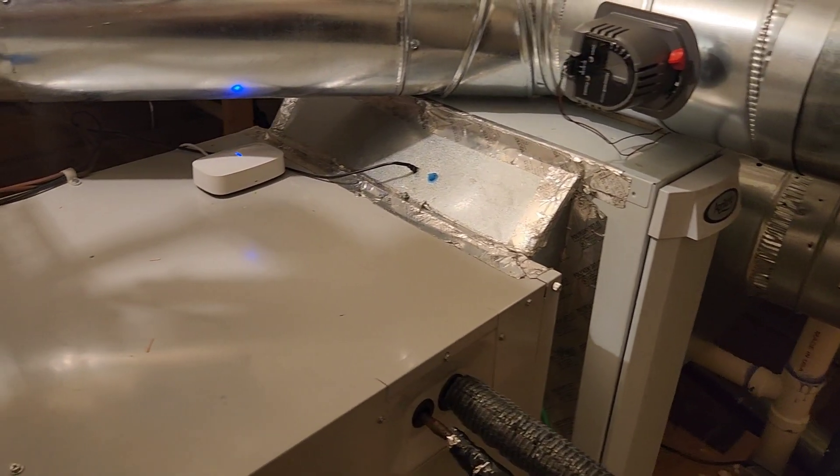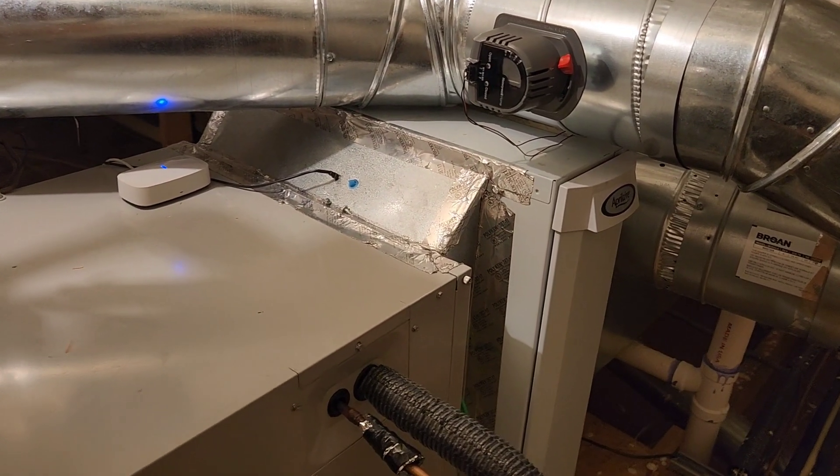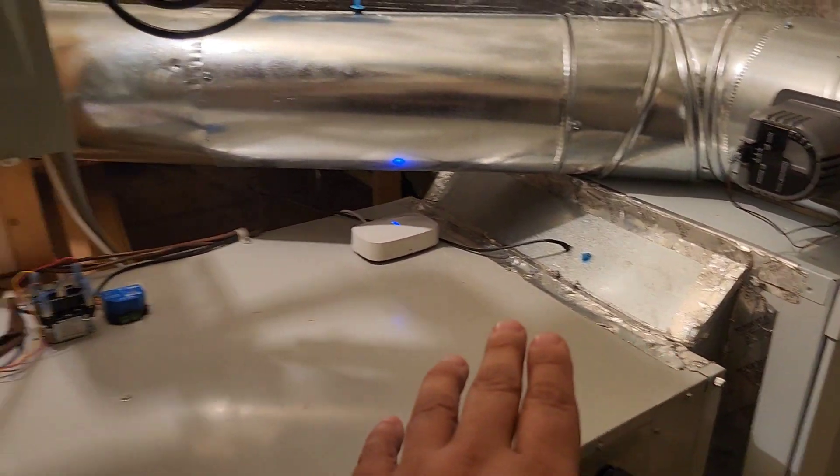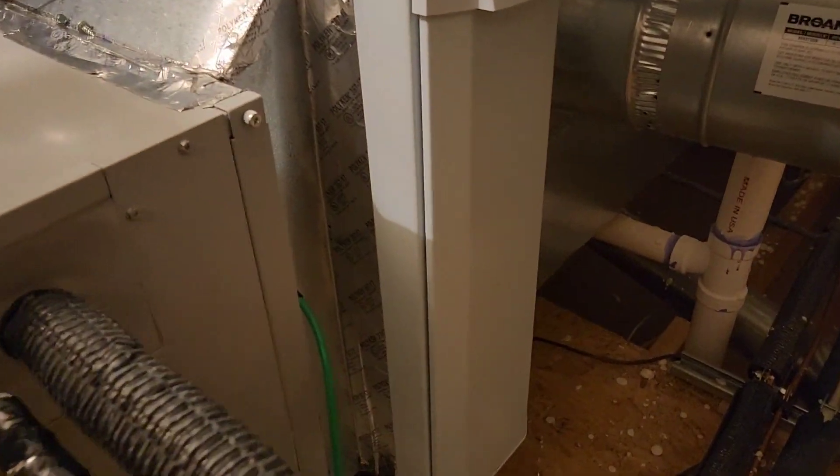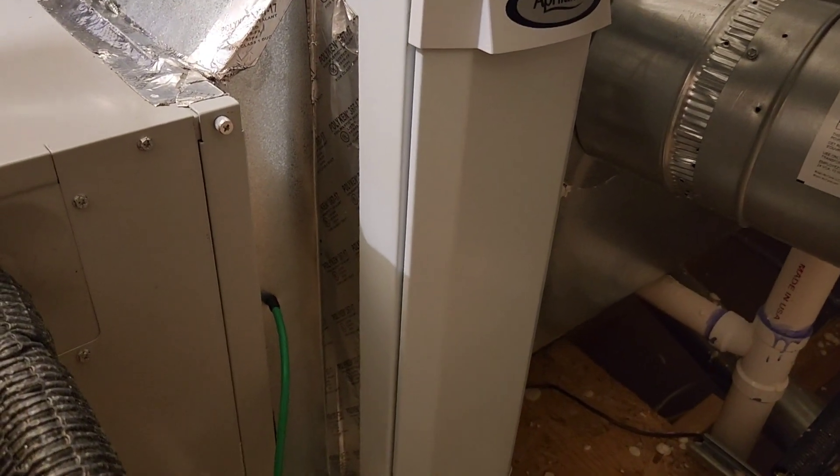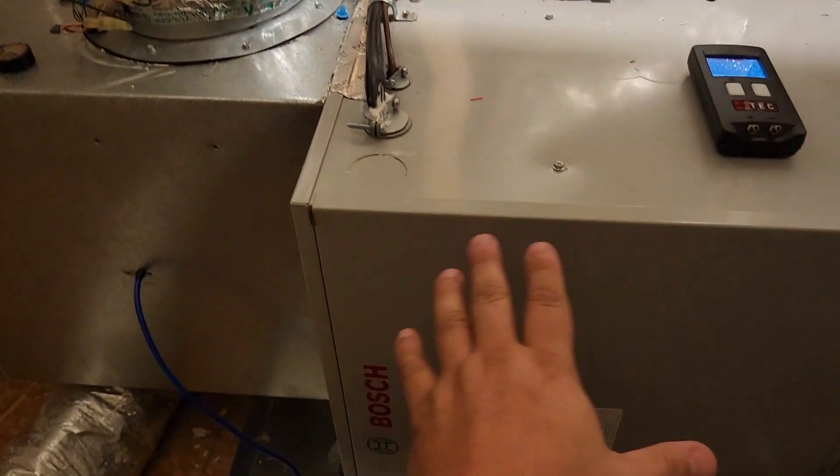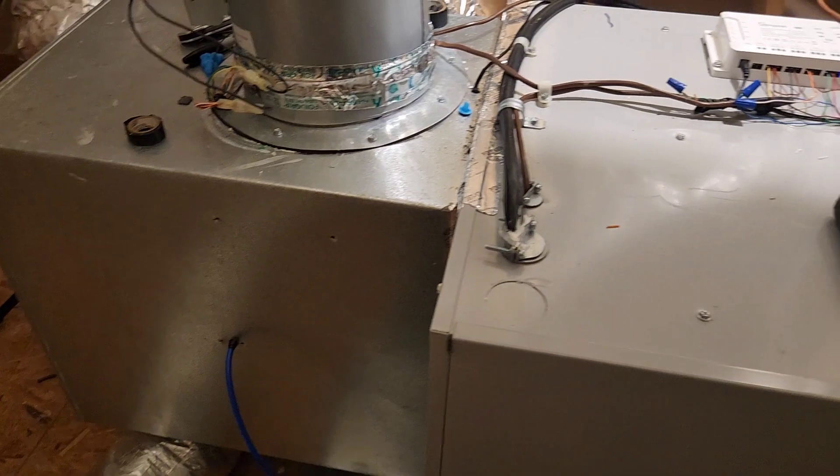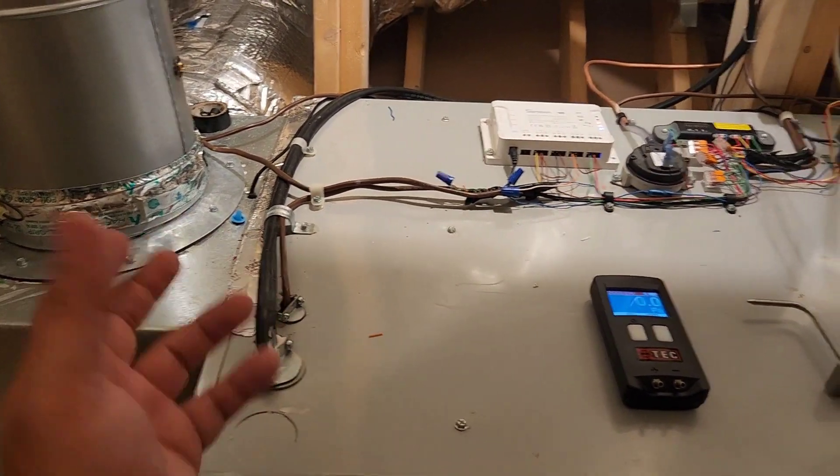The other thing to consider is where we put our test ports. Now, I didn't say holes, I said test ports, because when we drill holes in ducts in HVAC, we are not drilling holes, we are installing test ports. So we want to install the test ports immediately before and after the air handler, because that is how the system was tested in the lab. So if you notice, I've got a media filter kit here, but I will be reading the static pressure immediately before my air handler, not on the entering side of that air filter, rather between the media filter and the air handler. Same thing here in the supply duct. Again, I want to remove anything that might be in the way. Now, what do you do when you have a furnace and cased coil? A lot of times these cased coils are butted right up to a furnace. Where would you read your supply static? Well, let's flip over to a previous video I did a few years ago with the furnace that we had installed, and I'll show you where to put your static pressure test ports there. Then we'll come back to this video.